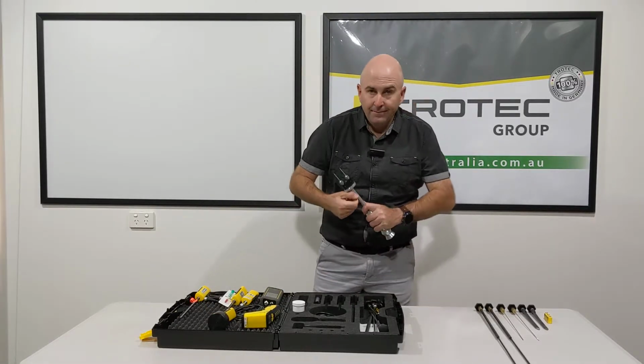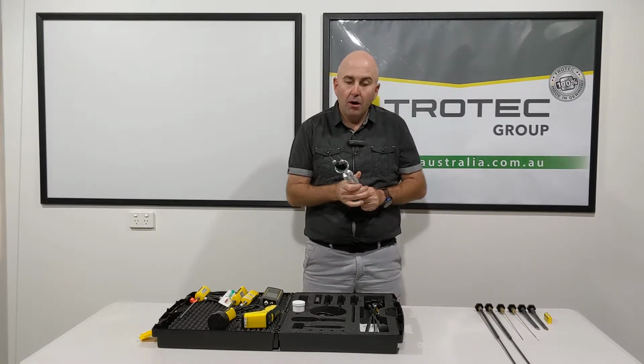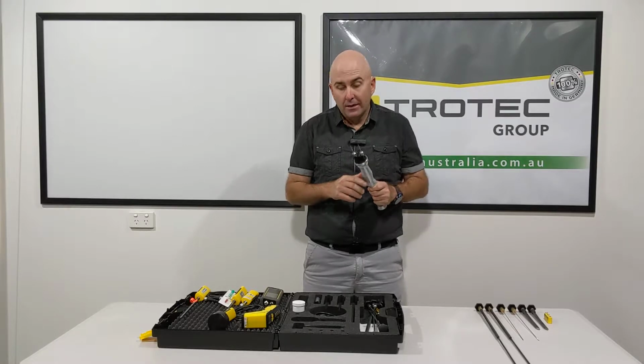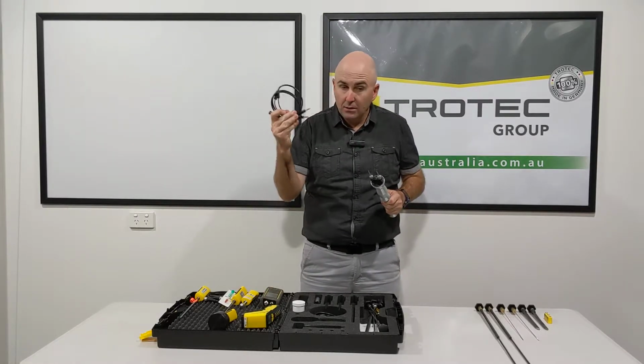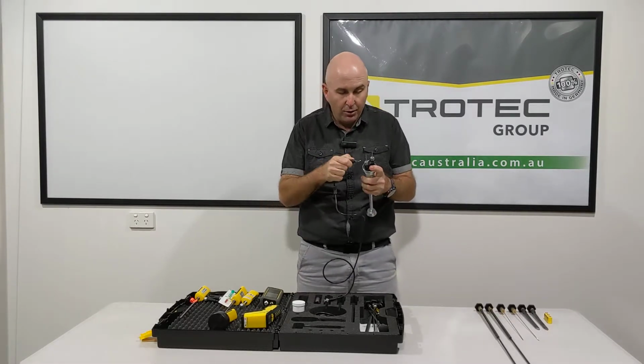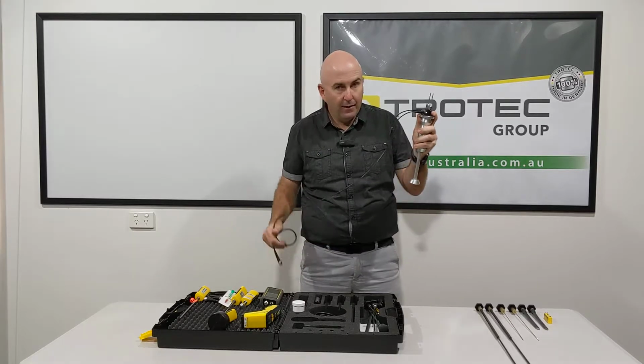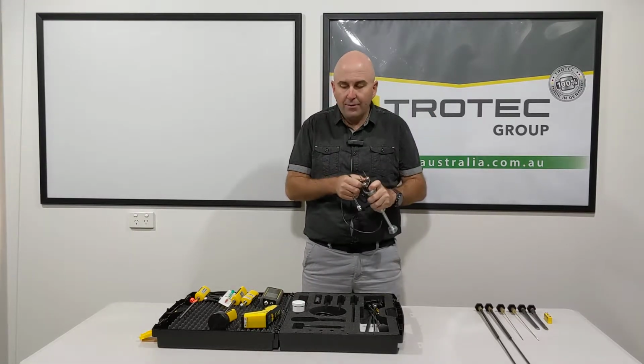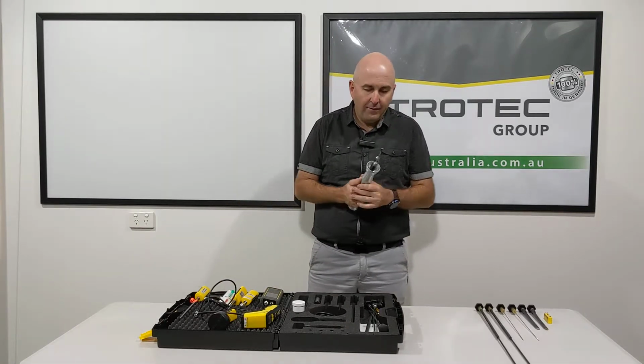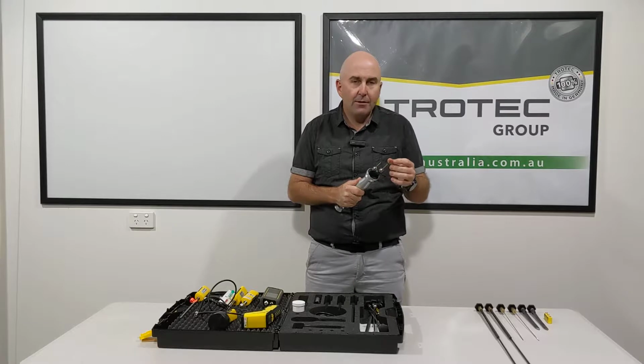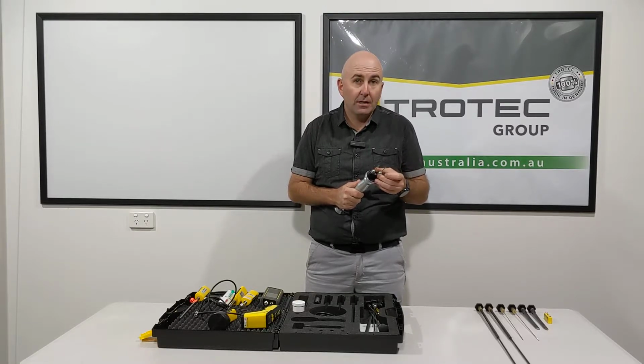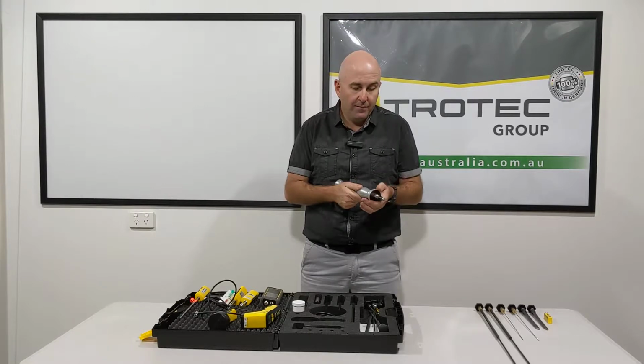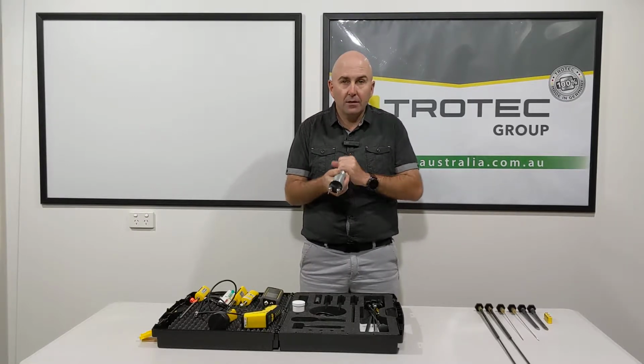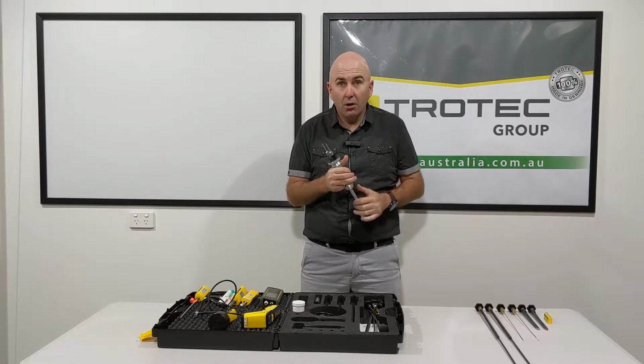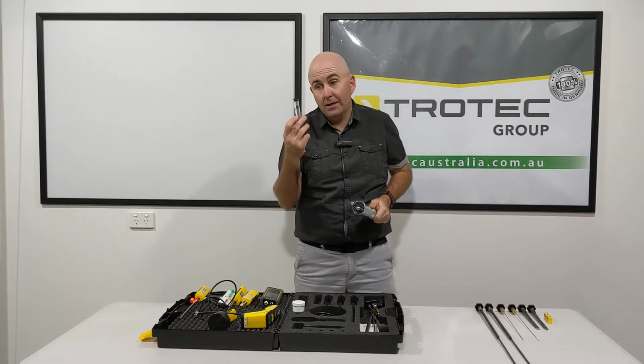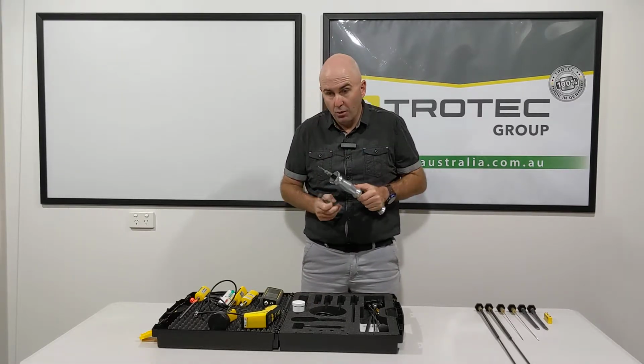Now, also you get a hammer probe. With the hammer probe, I've got 60 mil insulated pins. Obviously, there's a cable that attaches to the hammer probe. I'll just show you how that works. We pop that in and pop that in, and then that talks back to our meter. The fundamental of how this hammer probe is designed is they're very sharp pins, so they're not breaking as much as some of the other brands that are out there. It's got a very good slide on the surface area, so the pins aren't bending and breaking as much, so they're longer lasting. You do get a pack of 10 insulated pins that come with your hammer probe.